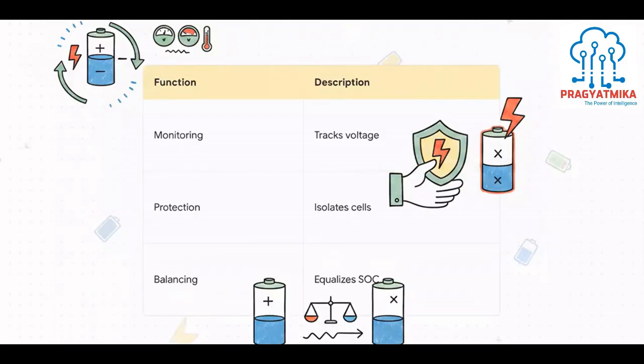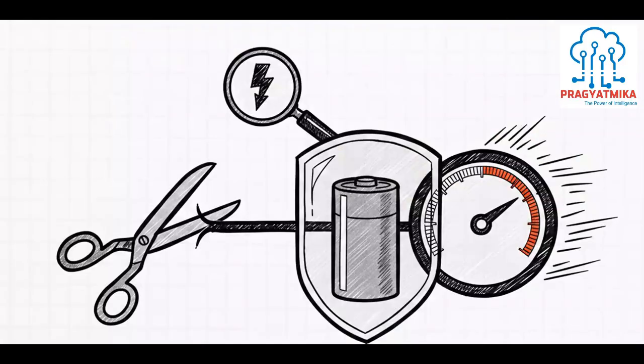Pretty smart, right? And to pull all of this off safely, especially in high-energy utility applications, the BMS has to operate at just staggering speeds. We're talking about critical measurements for voltage and current being sampled at 10 to the power of -3 seconds. That is literal milliseconds. This absolute precision is non-negotiable because modern lithium-ion cells simply do not tolerate overvoltage. By sampling data this incredibly fast, the BMS can instantly trigger physical contactors to isolate the battery pack before a tiny electrical anomaly cascades into a full-blown catastrophic failure.